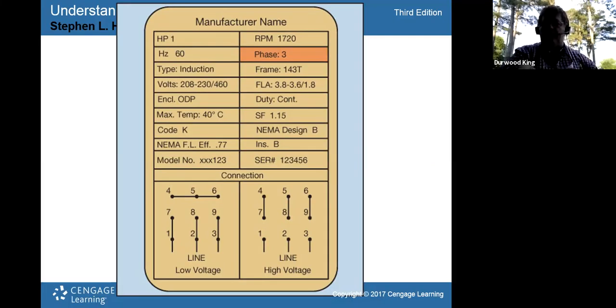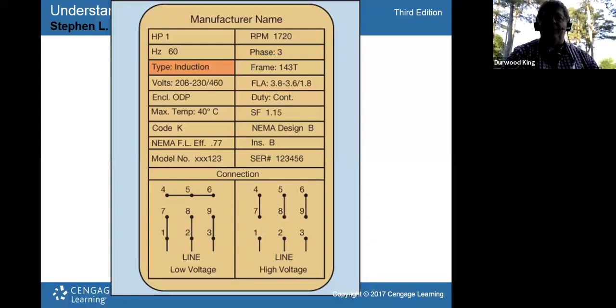And then there are some odd motors called two phase, and they're going to show those in this chapter. Those have two hots and a neutral. So it's two hot wires and a neutral. But I've never seen a two phase in person. They just show them in the book, but they're not common. And then the type of construction of the motor inside. When you look at the guts of the motor, how are the windings constructed? Is it an induction motor, or a synchronous motor or a wound rotor? There are different constructions of motors.